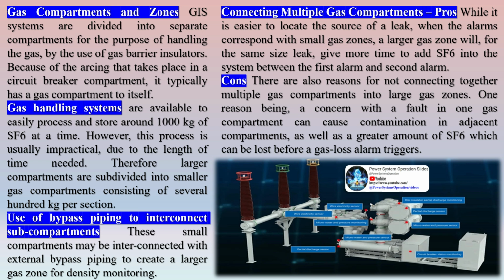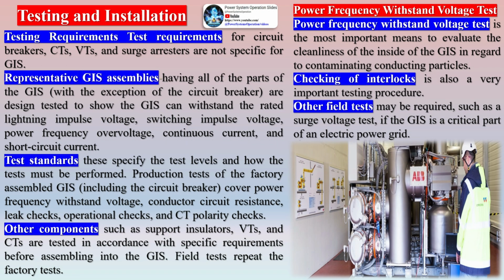Use of bypass piping to interconnect subcompartments. These small compartments may be interconnected with external bypass piping to create a larger gas zone for density monitoring.